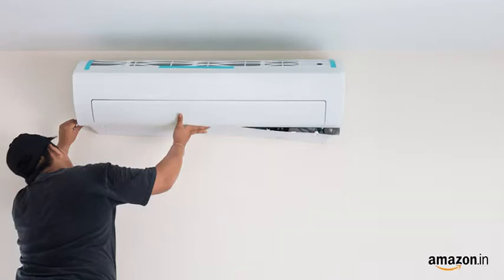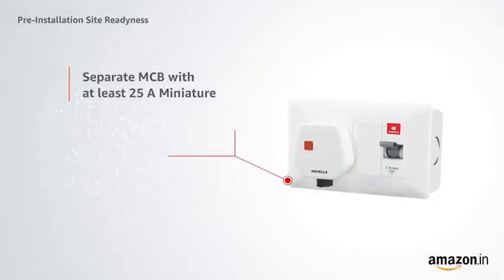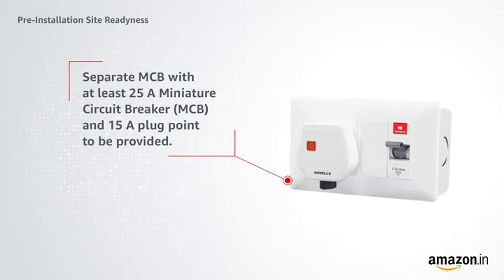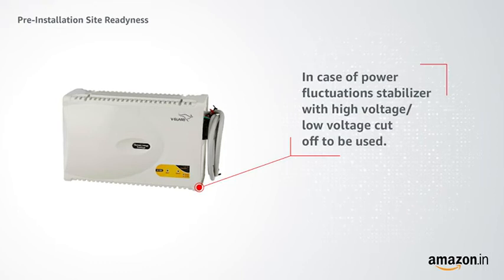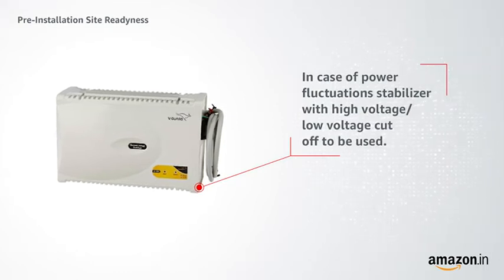Pre-installation site readiness: a separate MCB with at least 25A miniature circuit breaker and a 15A plug point must be provided. In case of power fluctuations, a stabilizer with high voltage or low voltage cutoff should be used.